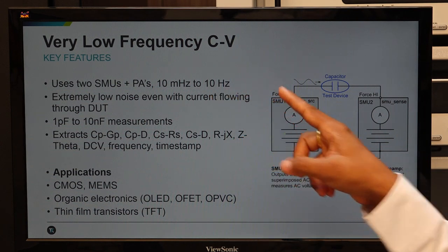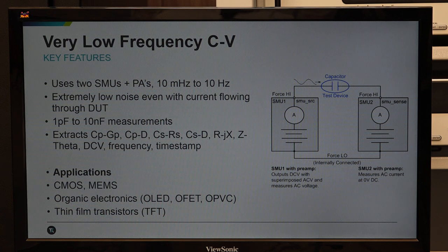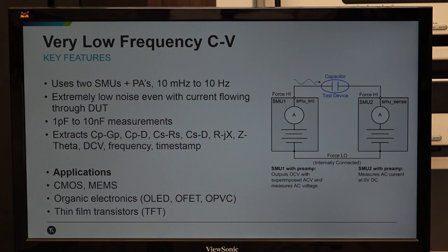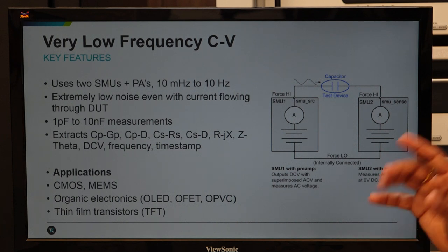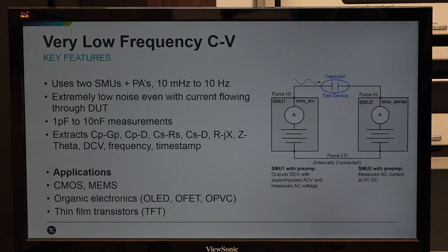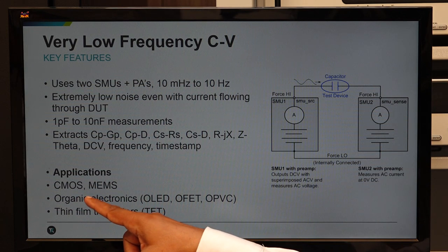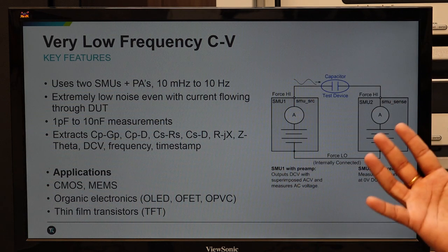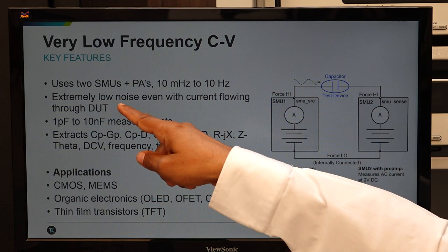For frequency-dependent measurement, quasi-static CV is further modified as very low frequency CV using SMU. CV measurement can be done for any device or material offering resistance up to 10¹⁵ Ohm. Two SMU plus pre-amplifiers are used, with frequency of operation from 10 millihertz to 10 hertz. Higher resistance is compensated by lowering frequency. Capacitance can be measured from 1 picofarad to 10 nanofarad. Parameter extraction is possible with models like series capacitance, shunt capacitance, dissipation factor, leakage resistance, imaginary and real resistance. Many research papers have used this for CMOS, MEMS, organic electronics, and thin film transistors.